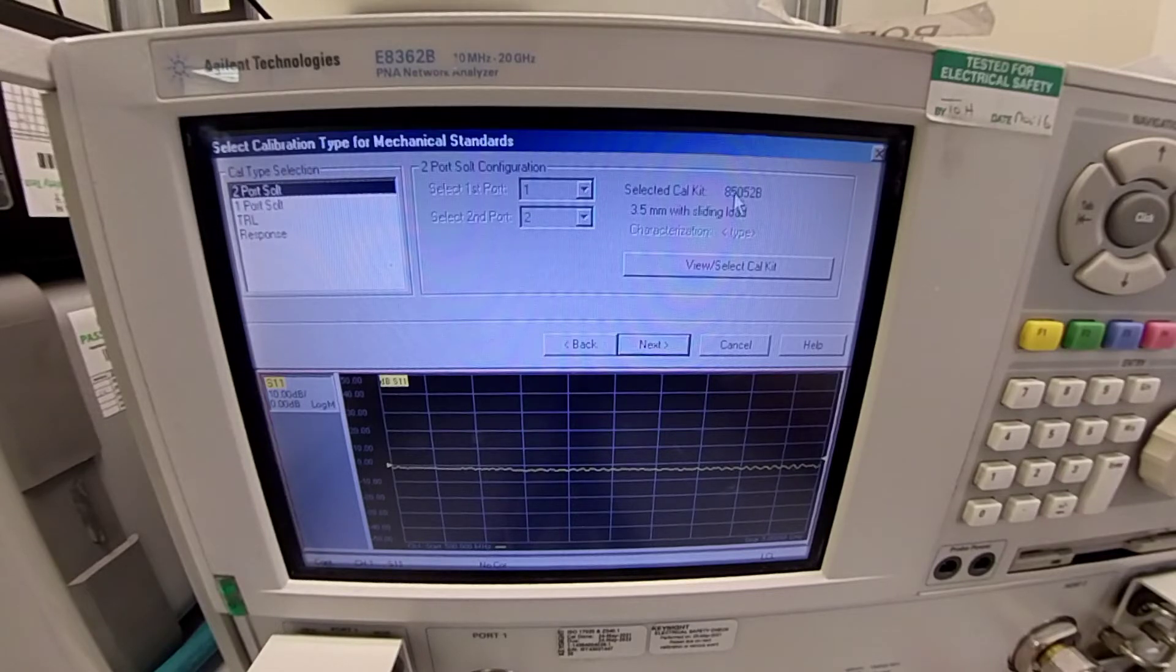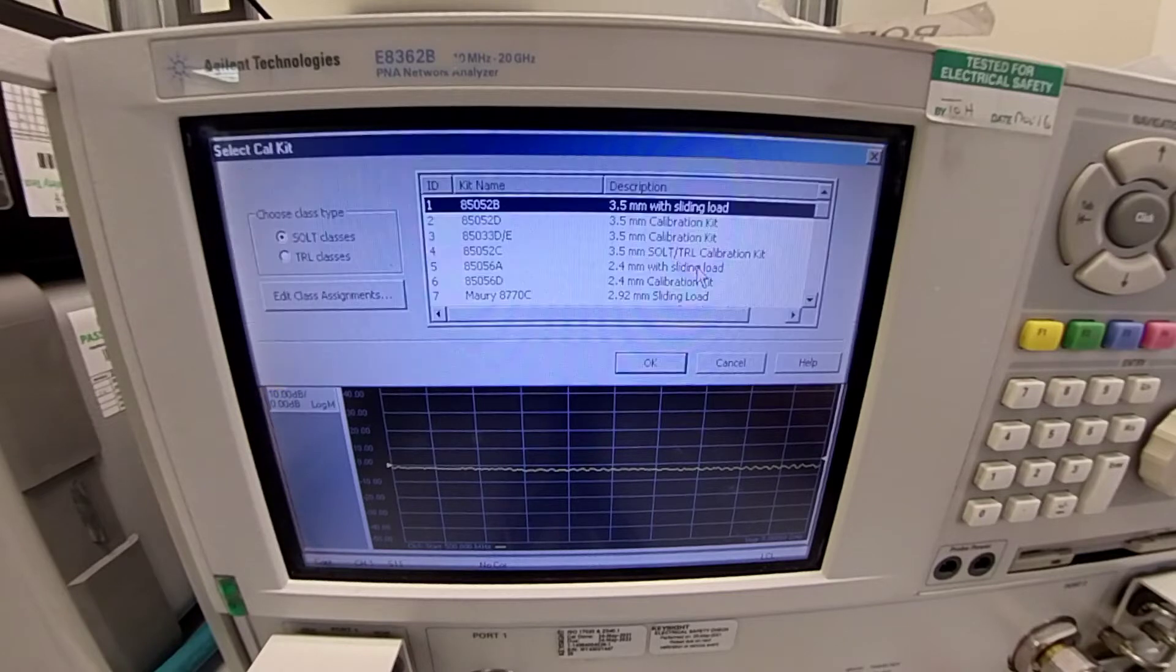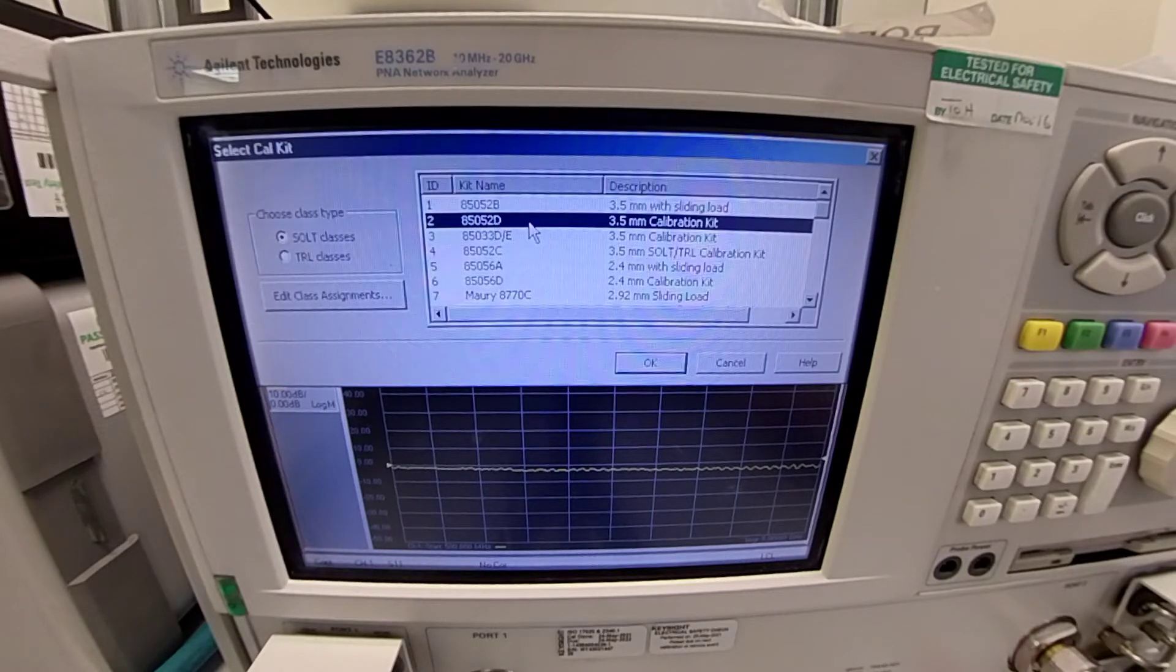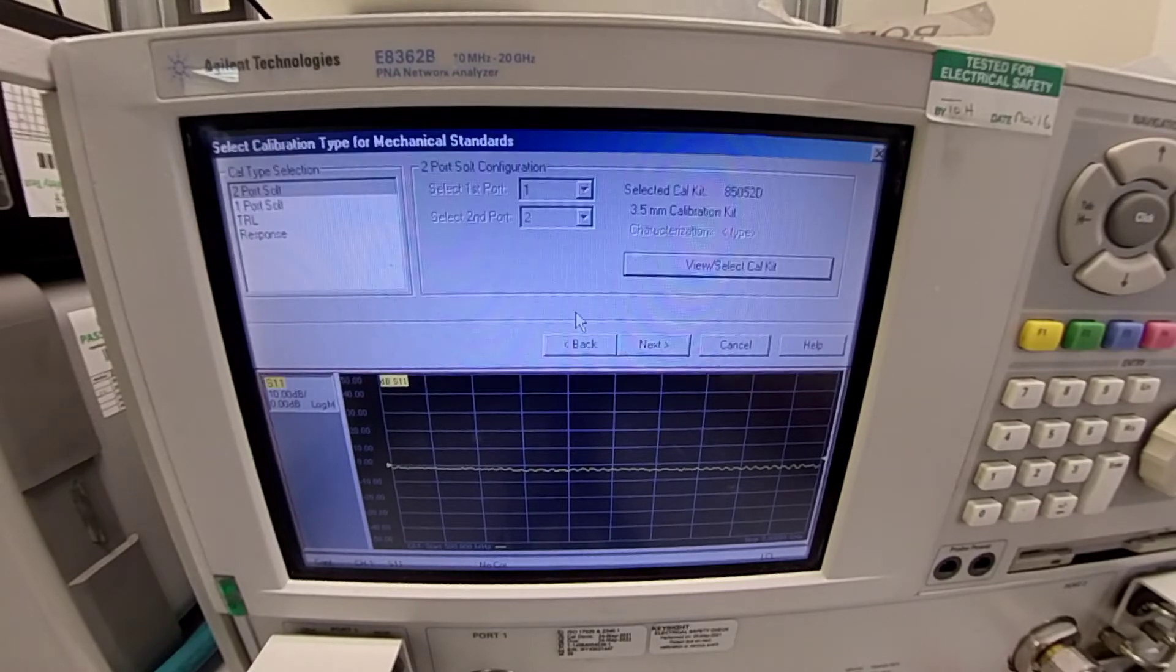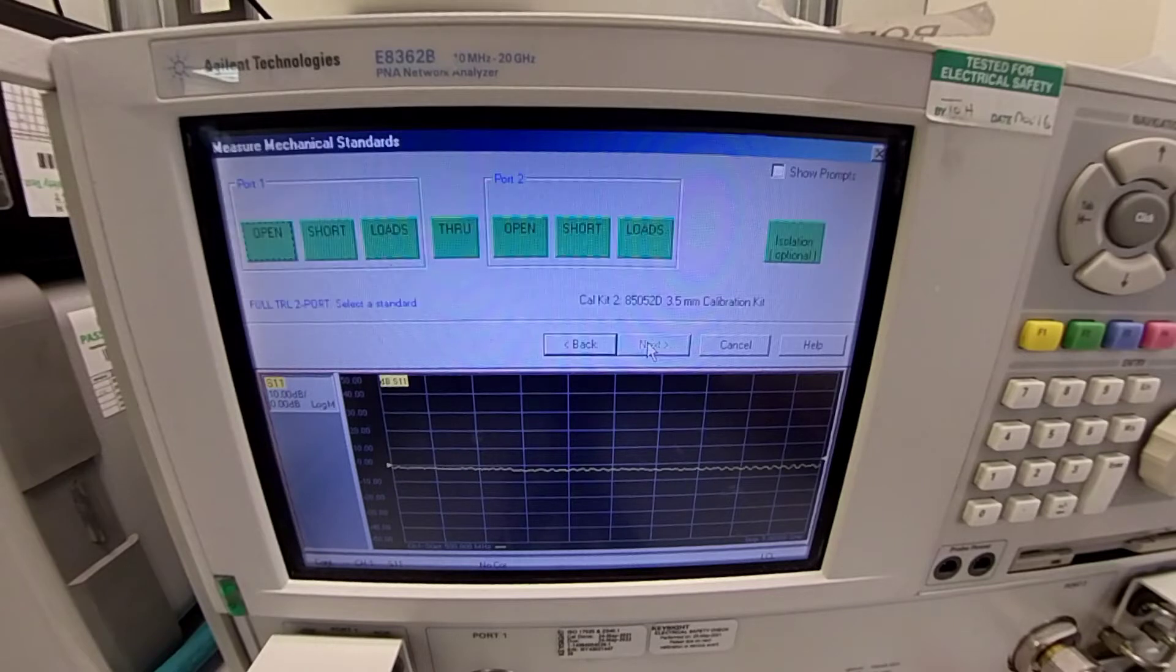The calibration kit is set to 850-52D, which is accompanied with this analyzer. You can select the kit of your own choice, whichever analyzer you are using. Select OK and press Next. As you can see, we have port number 1 and port number 2. We do it in a stepwise manner. First, we select and open port 1 and start the calibration process.